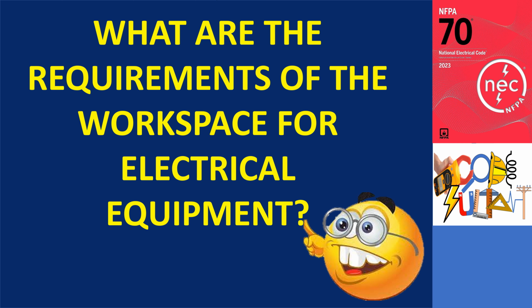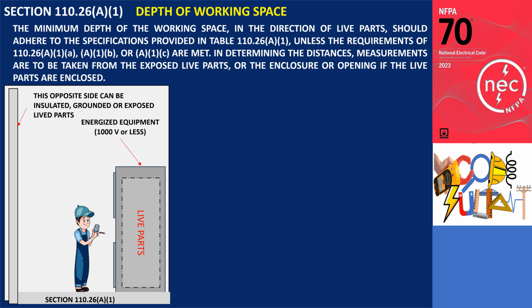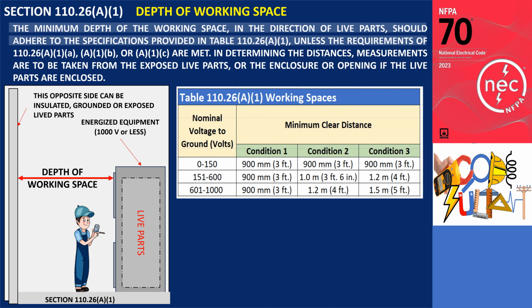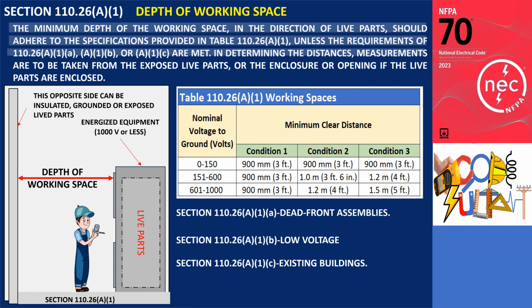What are the requirements of the workspace for electrical equipment? According to Section 110.26(A)(1), the minimum depth of the working space, in the direction of live parts, should adhere to the specifications provided in Table 110.26(A)(1), unless the requirements of 110.26(A)(1)(a), (b), or (c) are met. In determining the distances, measurements are to be taken from the exposed live parts, or the enclosure or opening if the live parts are enclosed.